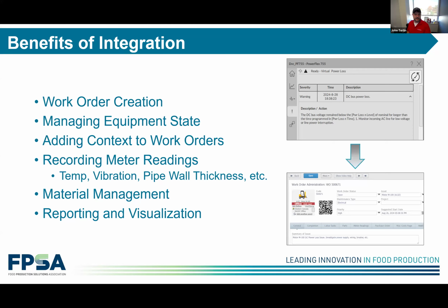The next two points go together regarding context. Take the pump example Tony gave earlier: a vibration sensor on a pump constantly feeds data into the CMMS via an edge device. If I use my mobile app, scan the QR code on the pump, or look it up in my S95 model, I can go to the meter readings tab and see a trend of that vibration over time. So when looking at historical failures or current state, if a work order was automatically created by AI or a control system, I can get more context before dispatching it to my team, all readily available within the CMMS.